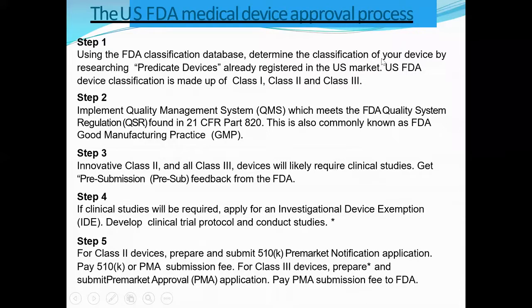First of all, you have to determine the classification of your device by researching the predicate device. Predicate device means what? In the pharma industry, we call it reference, standard, and test. The test is your product, and the reference is somebody else's product based on which you have developed yours. In the case of medical devices, we call it the predicate device, which has already been developed by somebody else and is already available in the market. So we have to see which predicate devices are similar to our own product and categorize accordingly, looking at how others have categorized those devices. Say, for example, I want to get marketing approval for an IR thermometer in the US FDA.